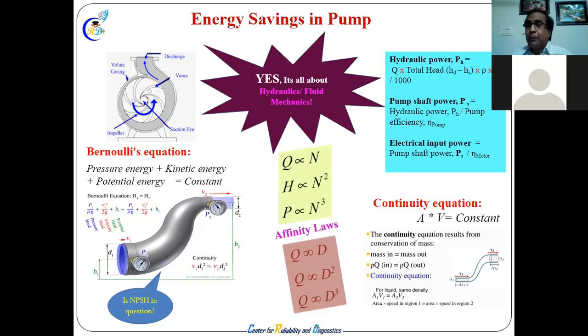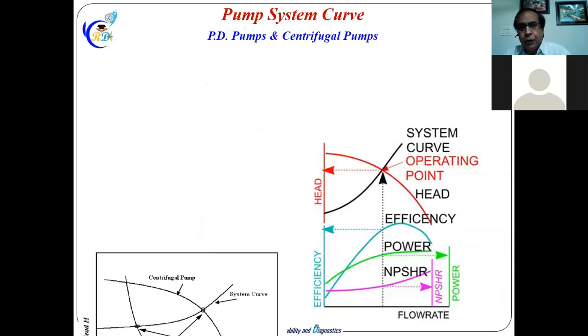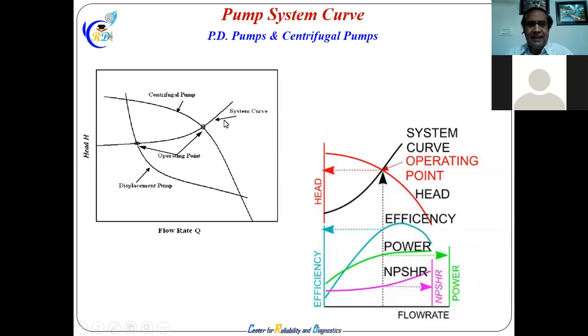So that means we have to take care with the VFD. What is the driven machine doing? The driven machine has to do its job the way this formula demands. So this formula is like this. For a displacement pump, the flow comes like this, and the centrifugal pump HQ curve looks like this. And system curves, if you put either a centrifugal pump or a positive displacement pump for a particular system curve.